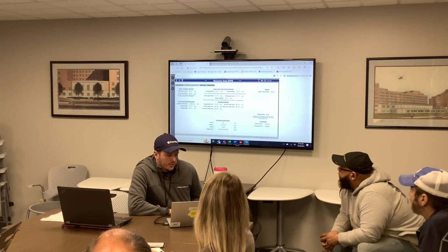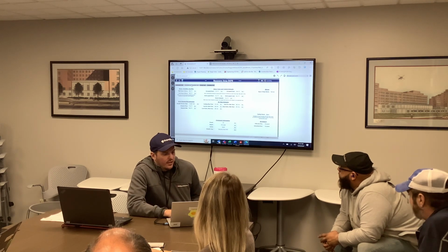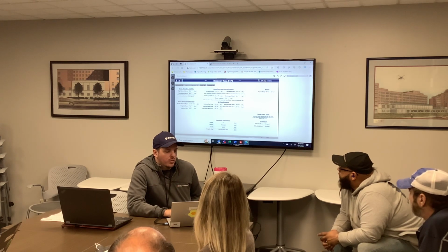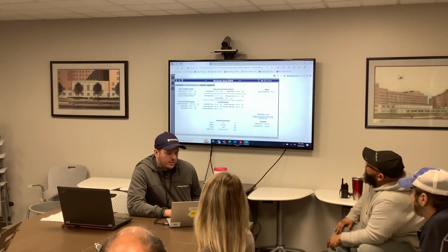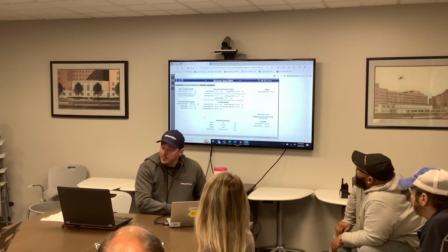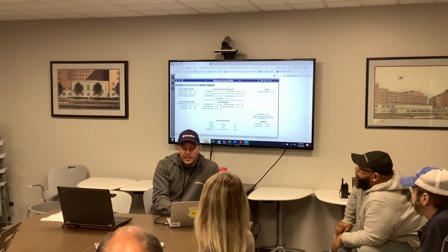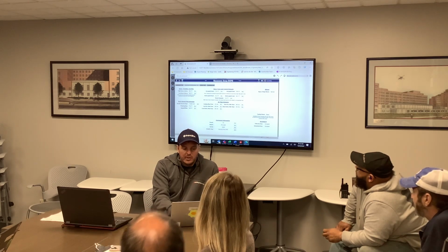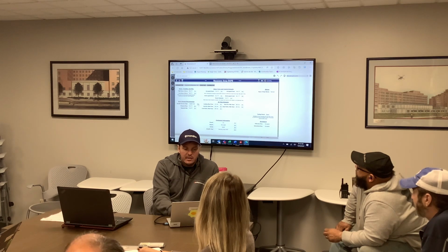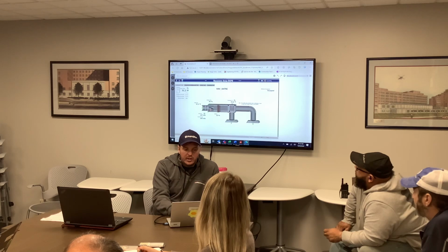If we go to our set points configuration page, this is set up pretty much the same way as the other stat. You have your occupied heating and cooling. You do have a center set point you can set here, which will automatically shift these two around for you. And then you can disable the stat through here. If you leave it enabled, you can give them a set point max and min. And again, you can see what they're doing by the effective set points.